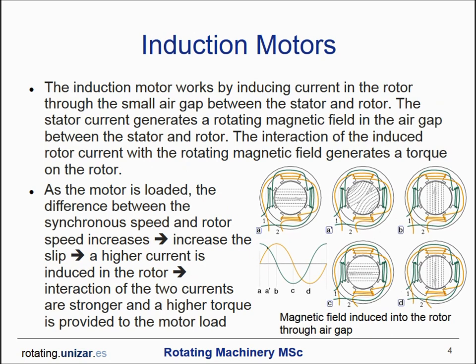Let's review how both motors work. The induction motor works by inducing current through the small air gap between the stator and the rotor. The stator current creates a rotating magnetic field in this air gap, and the interaction of the induced rotor current with the rotating magnetic field generates a torque on the motor. The induction motor is self-regulating, meaning it can adjust torque to match the load demand without additional regulation equipment. If there is no load on the shaft, the rotor runs at a speed slightly less than synchronous speed — this difference is called the slip.